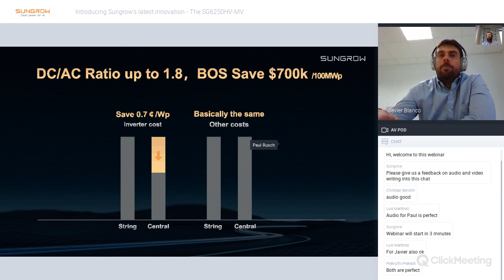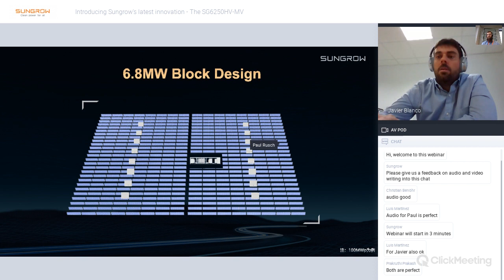The block design can achieve up to 6.8 megawatts. This is what we are considering with this MV station, and it's in the range of the optimized block size for these large utility PV plants. I think it's something shared by all the players in the industry that a PV block between 6 and 7 MVA is more suitable in terms of overall cost. This kind of block in the range of 6.8 megawatts can also reduce a lot of logistics by reducing the number of MV stations to be shipped to the same PV plant. So talking about the block size, I think it's in the suitable range in terms of reducing Capex, OPEX, and in the end LCOE too.